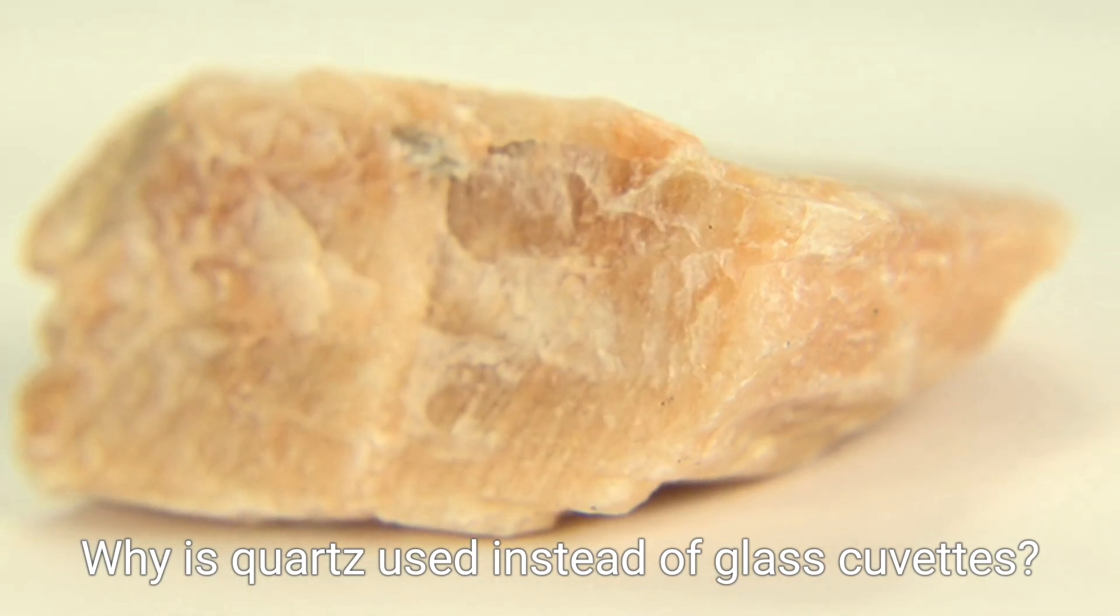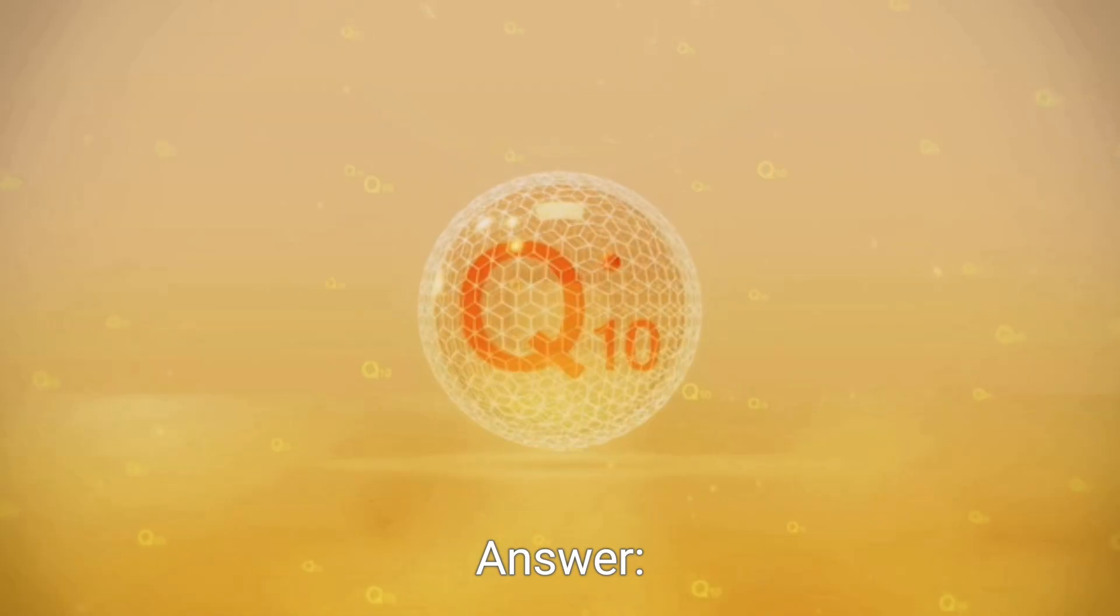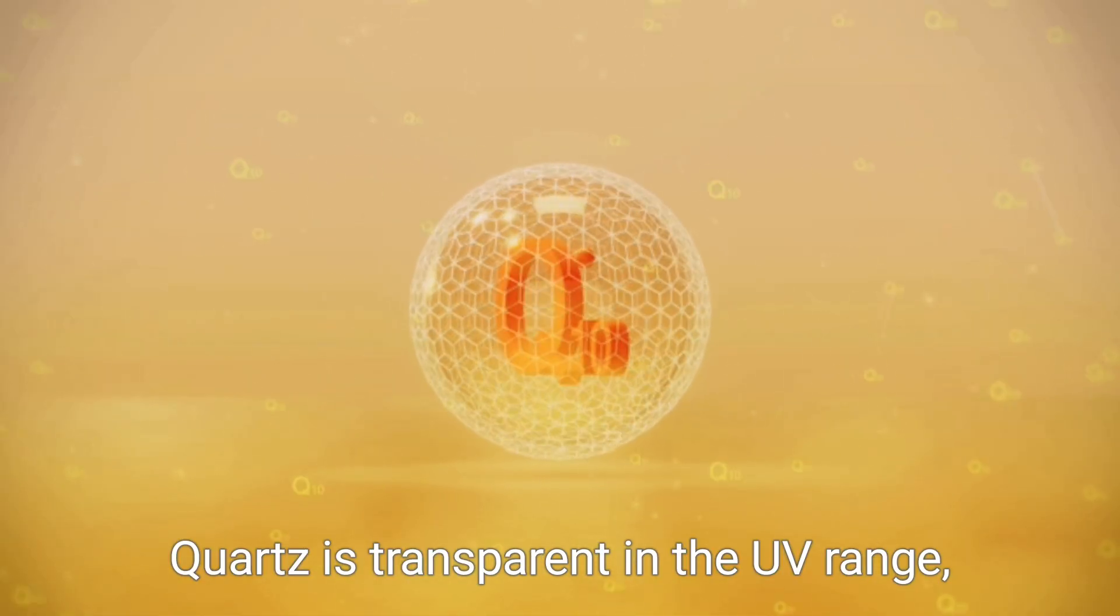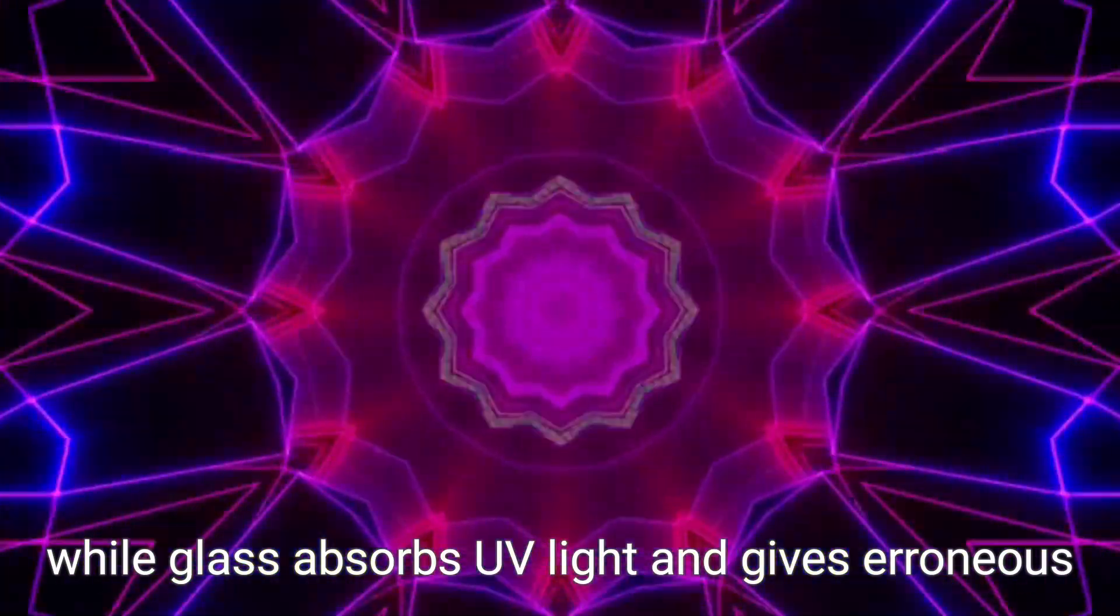Why is quartz used instead of glass cuvettes? Quartz is transparent in the UV range, while glass absorbs UV light and gives erroneous results.